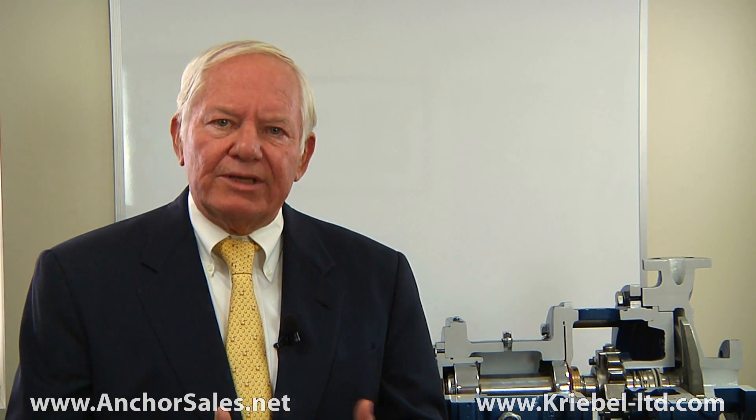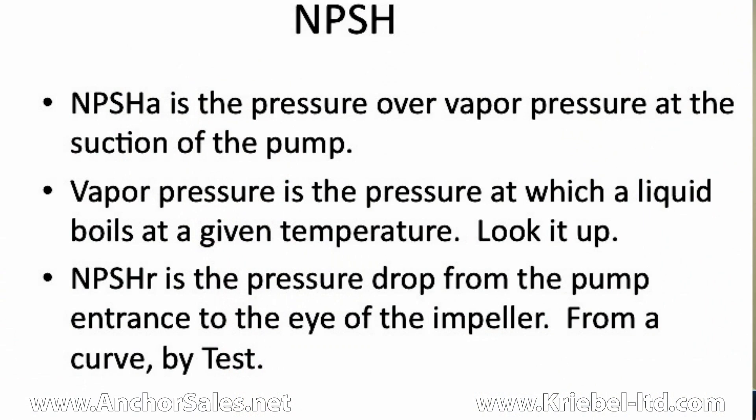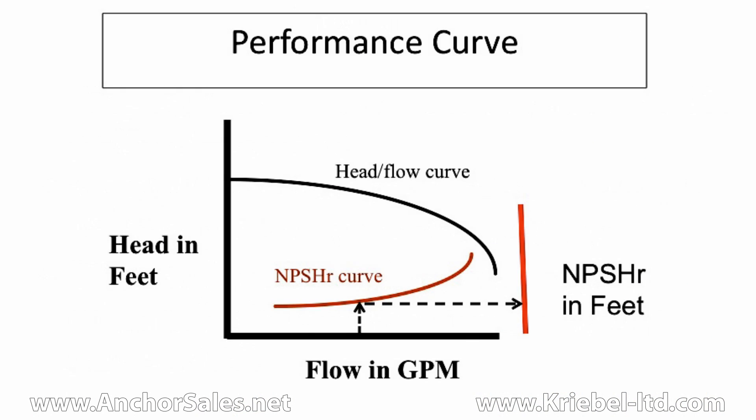Now, what is NPSHR? It is the pressure drop from the inlet of the pump to the eye of the impeller. It's determined by test and it's shown on the pump curve versus flow.